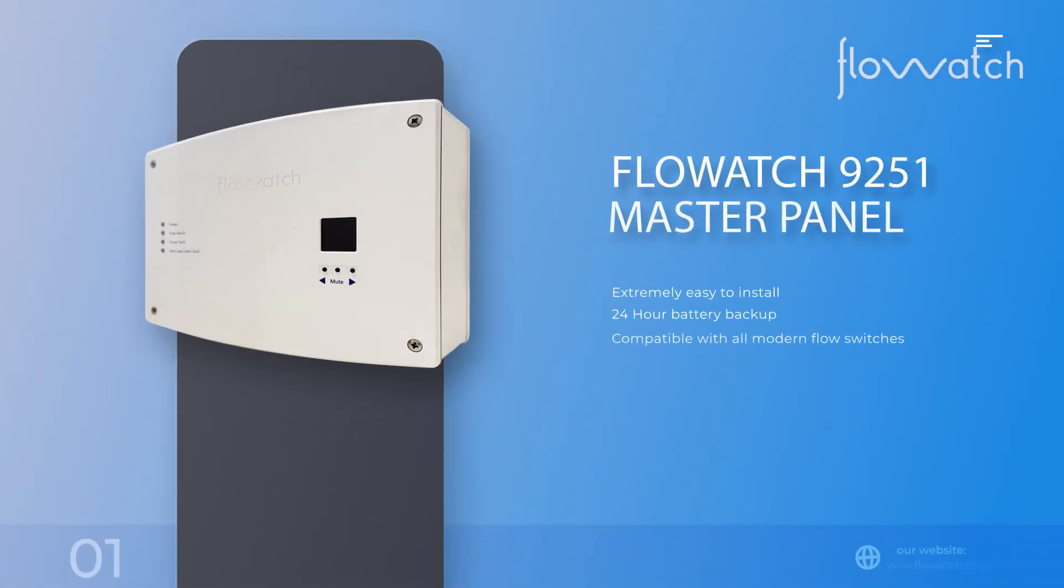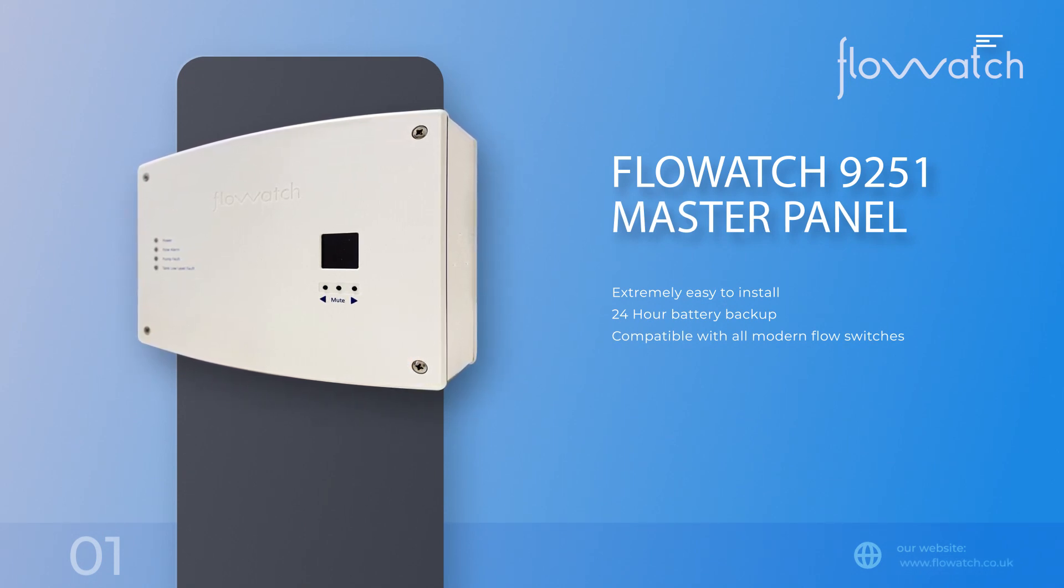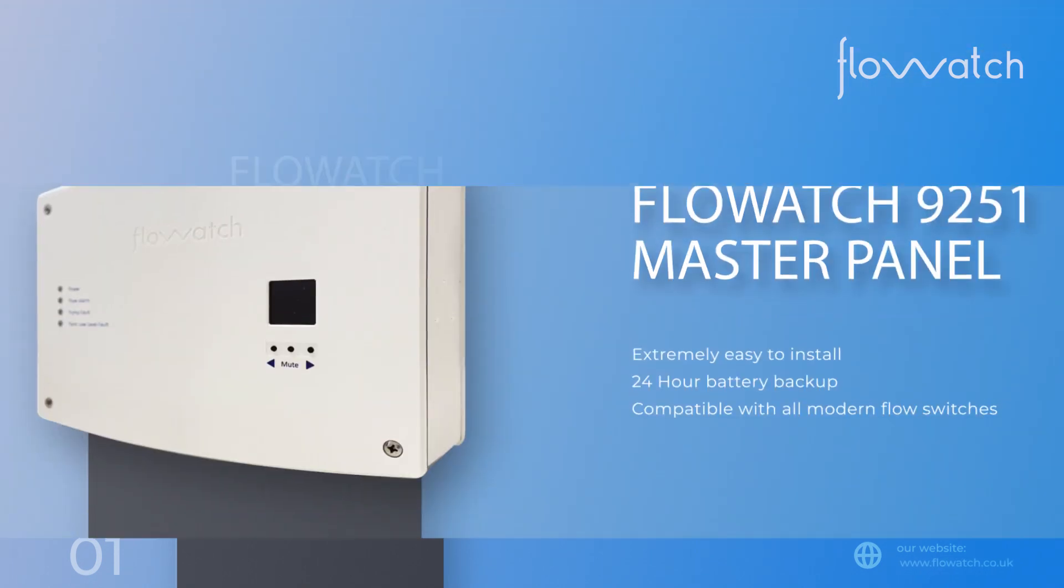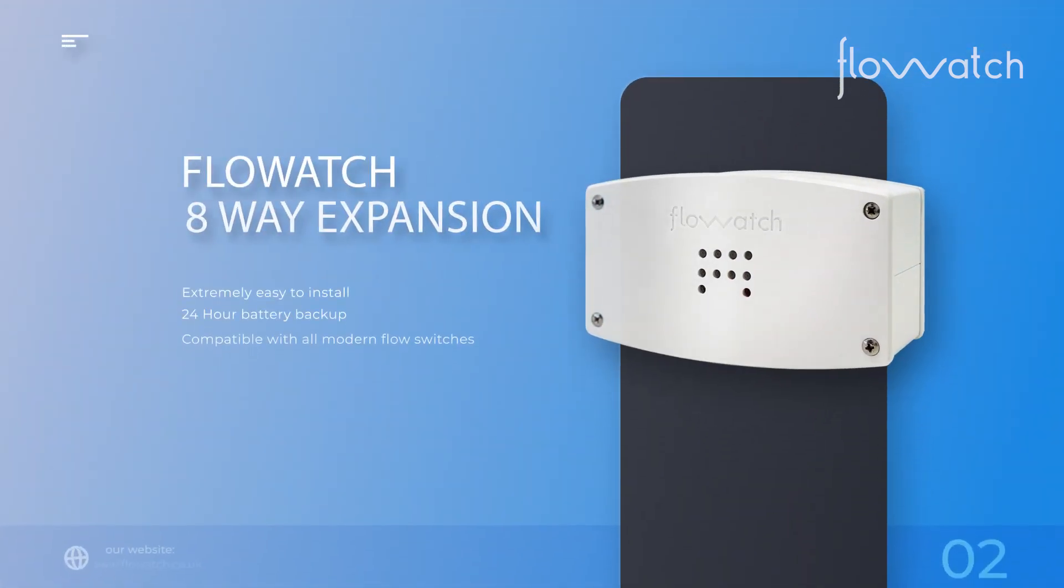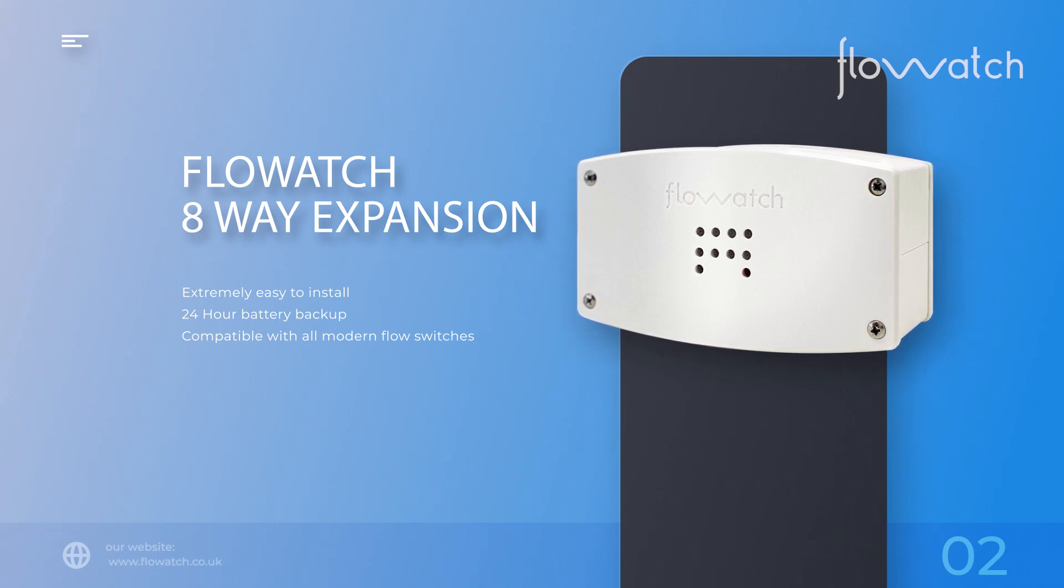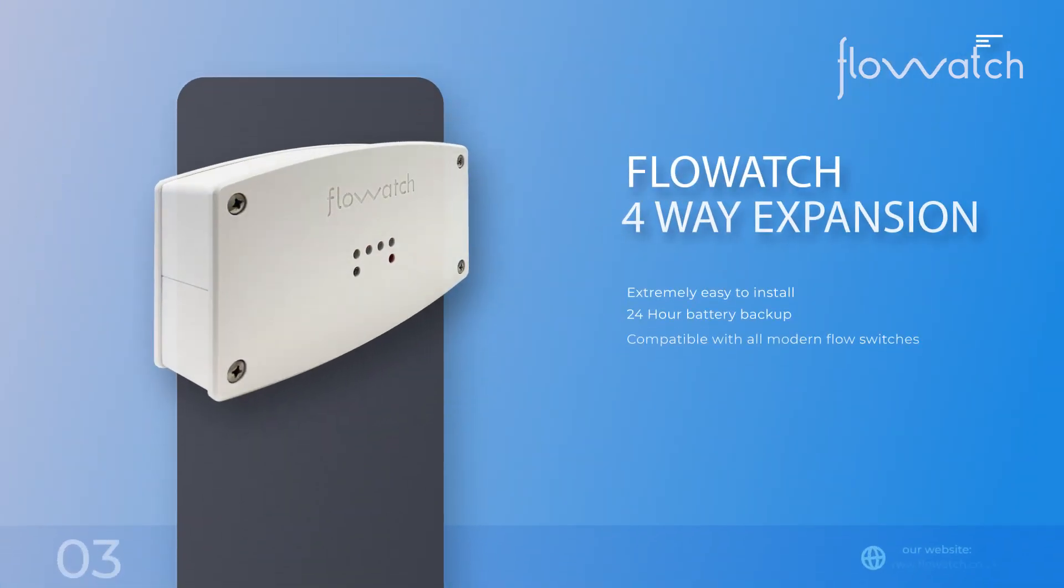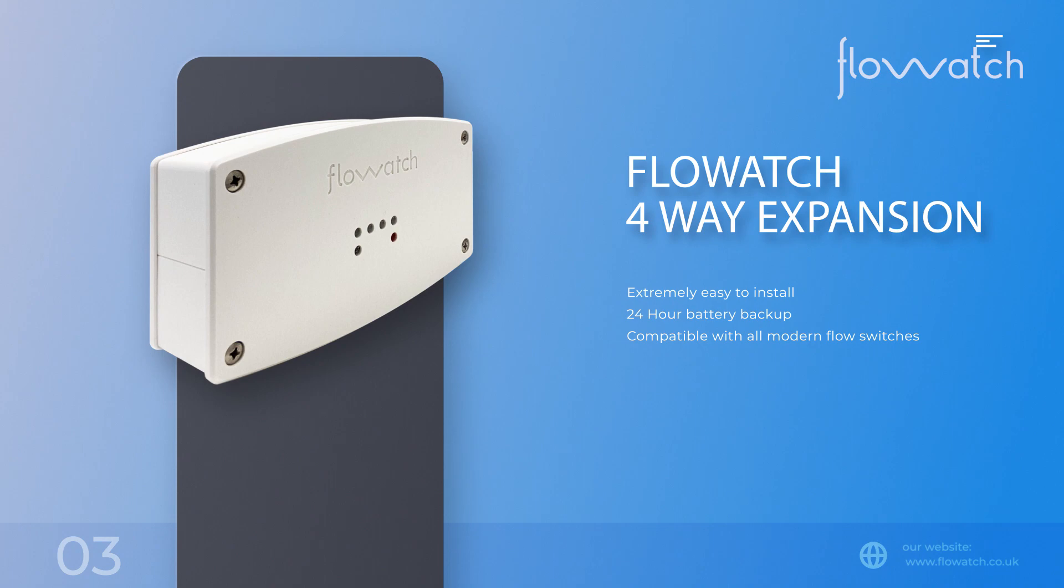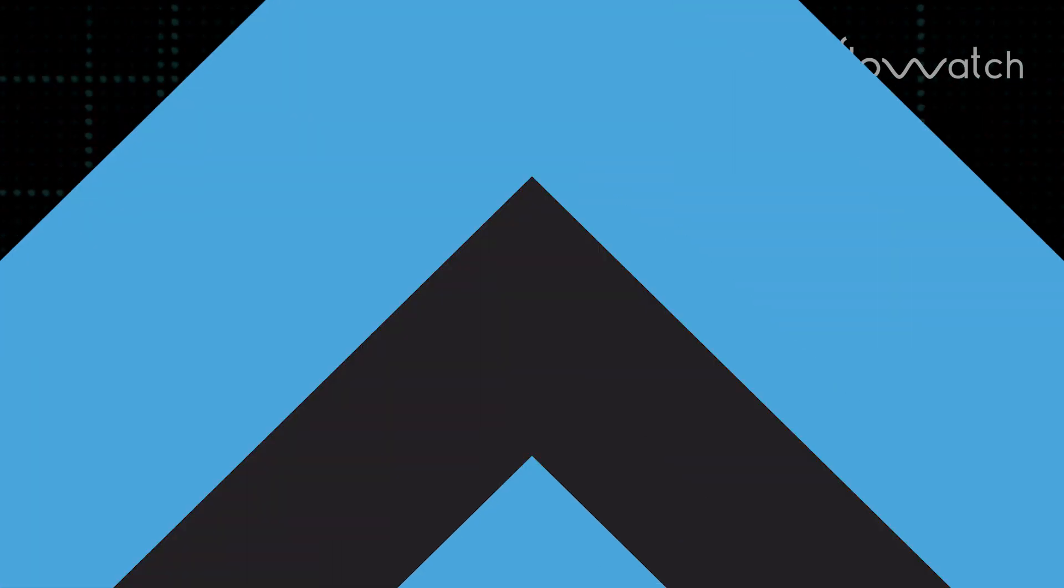To connect additional inputs to the expansion units, a two-core FP 200 1 millimeter cable is then connected to the field device as per master units, but installed into the local expansion module, reducing cost through length of cable run and enabling local detection should a fault occur on the system.